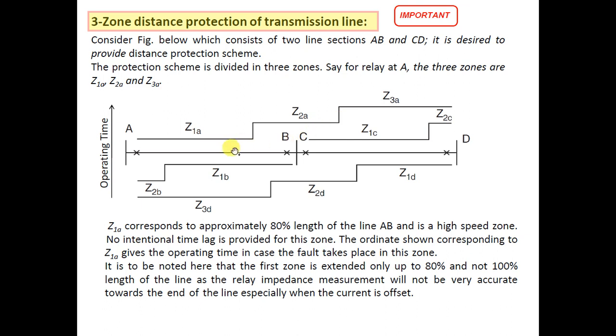In this manner, every point on the line is protected by at least three layers of protection — that is why it is called three-zone protection. For example, if a fault occurs at any point, the first layer might be Z1D, the second layer Z2C, and the third layer Z3A. Generally, the third zone of any relay — Z3A, Z3B, Z3C, Z3D — provides backup protection for the adjoining line.